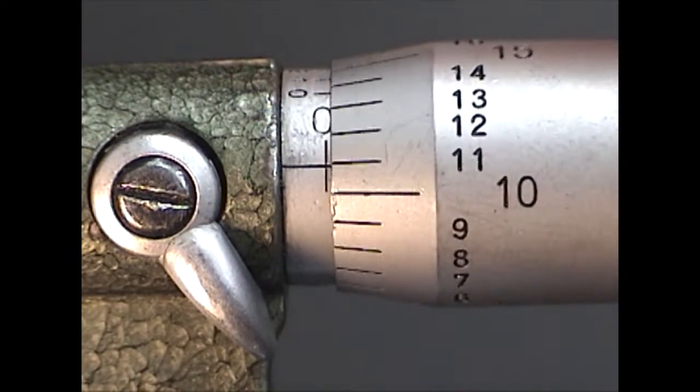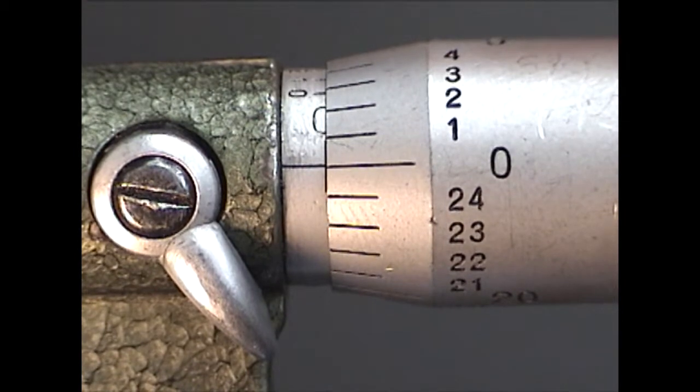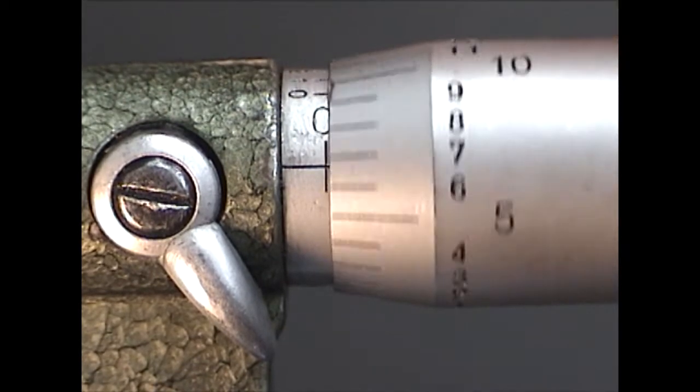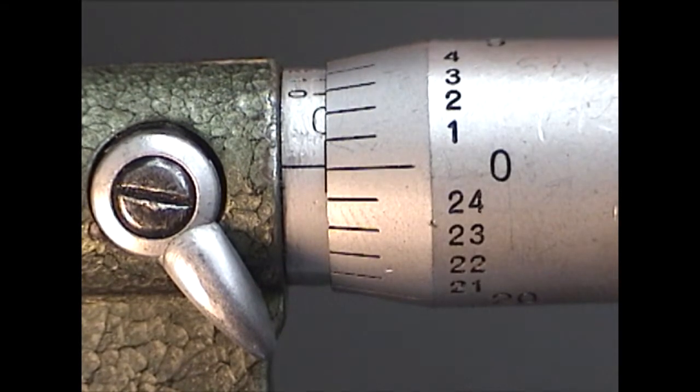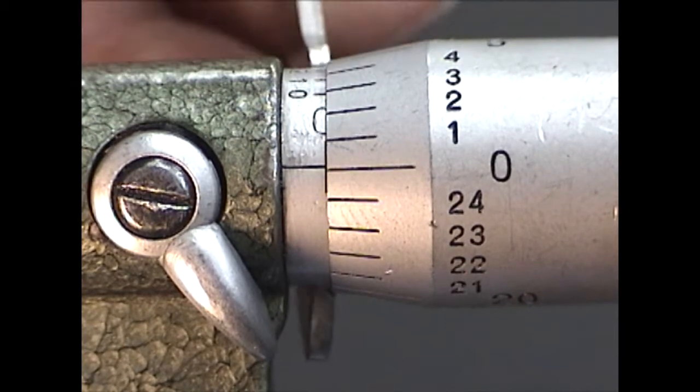After making an adjustment, open and close the micrometer several times, each time checking to see if the zero lines are properly lined up. If not, an adjustment will be necessary.